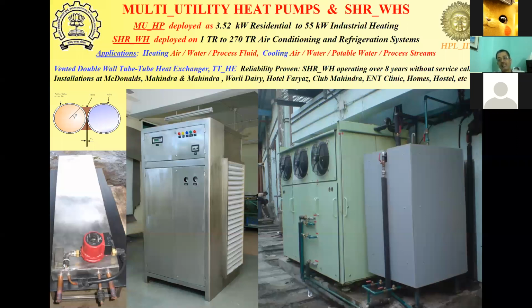In this case, the evaporator temperature was the same, 7.2 degrees centigrade, but the condensing temperature would be lower because we are recovering heat in the form of hot water. So part of the superheat would be recovered as hot water for sanitation, and then the desuperheated refrigerant would be evaporatively condensed in this particular unit. I will show you what patents we have deployed for evaporative condensation.